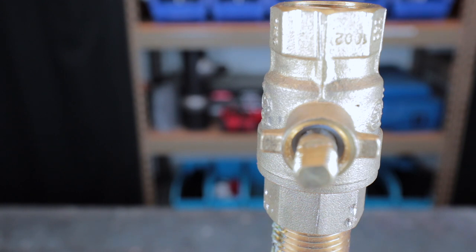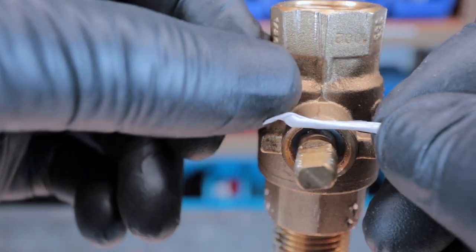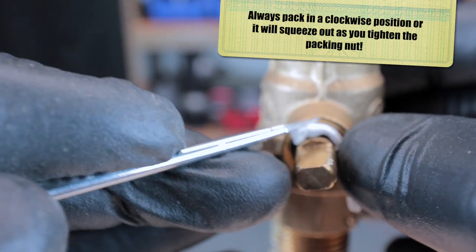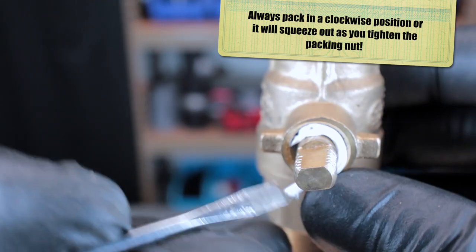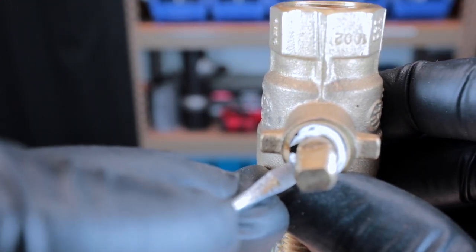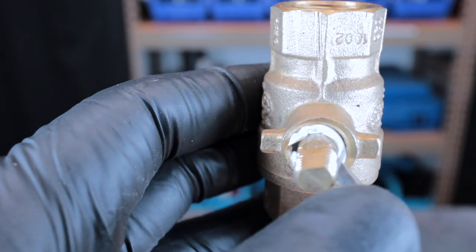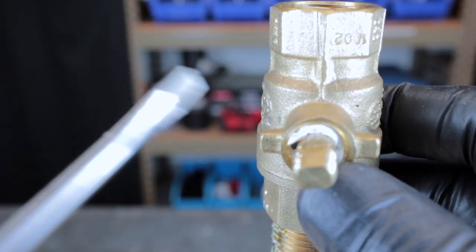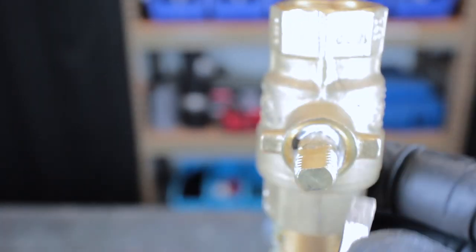Teflon's a little tough so I can get a pair of scissors here and I'll snip off a little piece of teflon. It's simply now just a matter of taking the little piece of teflon and then with a very fine little screwdriver or preferably like a jeweler screwdriver, you would go around the valve and you would proceed to push this in. You want to get it down pretty far because when you put the nut back you want it to push this all the way down to the bottom where that nylon washer is. You just go around it and continue to push it in. As you can see it's going in.